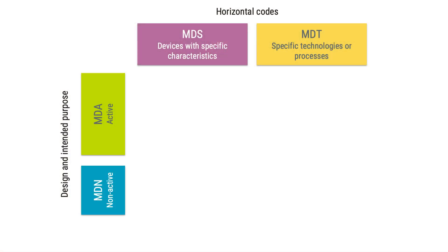I will start with the MDR codes for the Notified Bodies. They are published in the Implementing Regulation 2017-2185, so you will not find them in the actual MDR. There is a link under this video to this Implementing Regulation. These codes are divided into four categories. First, there are the MDA and MDN codes that relate to the design and intended purpose of the device. MDA codes are for active medical devices and MDN for non-active medical devices. Then we have so-called horizontal codes, divided into two categories: the MDS codes for specific characteristics of the medical device, and the MDT codes for specific technology or processes related to manufacturing.